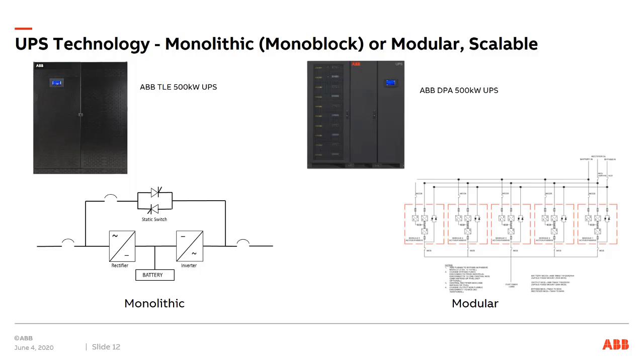What that essentially means is that the UPS is what it is. Historically, a 500 kVA UPS would have a 500 kVA rectifier, a 500 kVA inverter, and the static switch would support 500 kVA. That's all it knows, and that's what it can do. If customers need more power, they will just parallel another 500 kVA to that one, or more of them, to support additional power, or one extra one if they would like some redundancy.